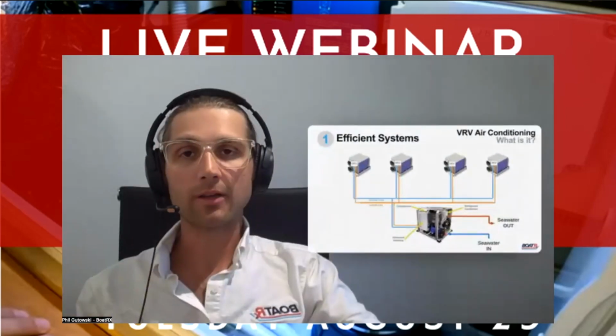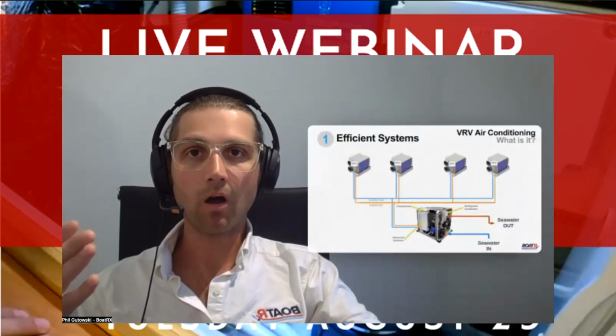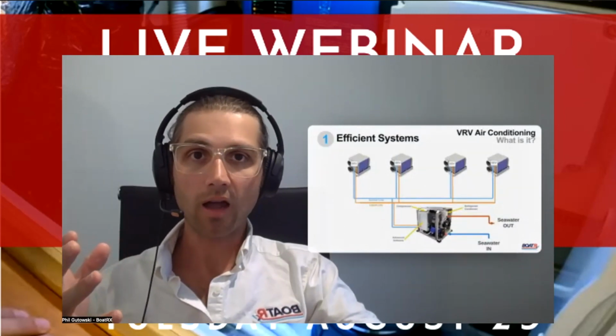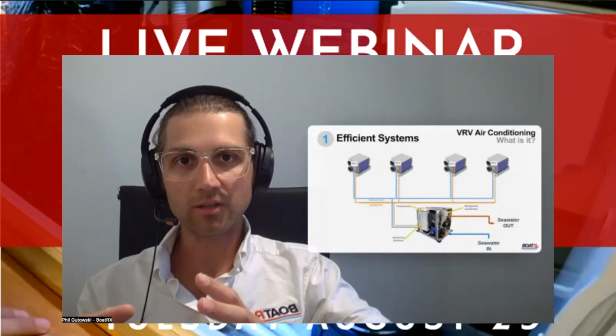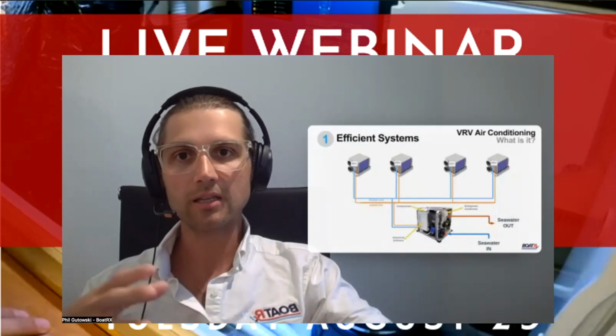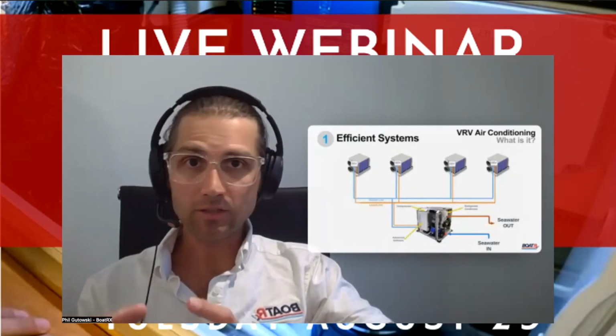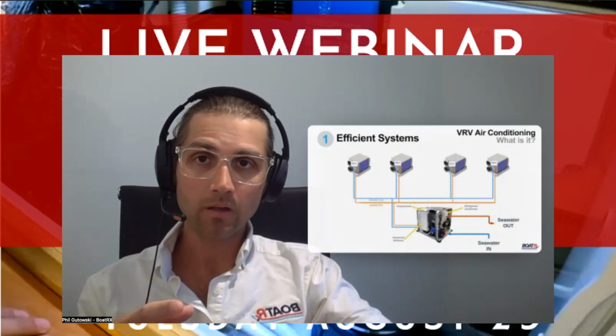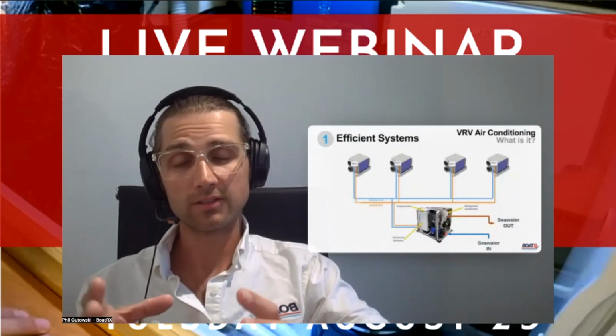The thing that's really special to point out here is that all of these components are connected to a common controls network, and it's software that's processing the data from a number of temperature and pressure transducers throughout the system to make changes to the compressor speed, fan speed, and expansion valve positions in real time to maximize both the comfort and the efficiency of the system.